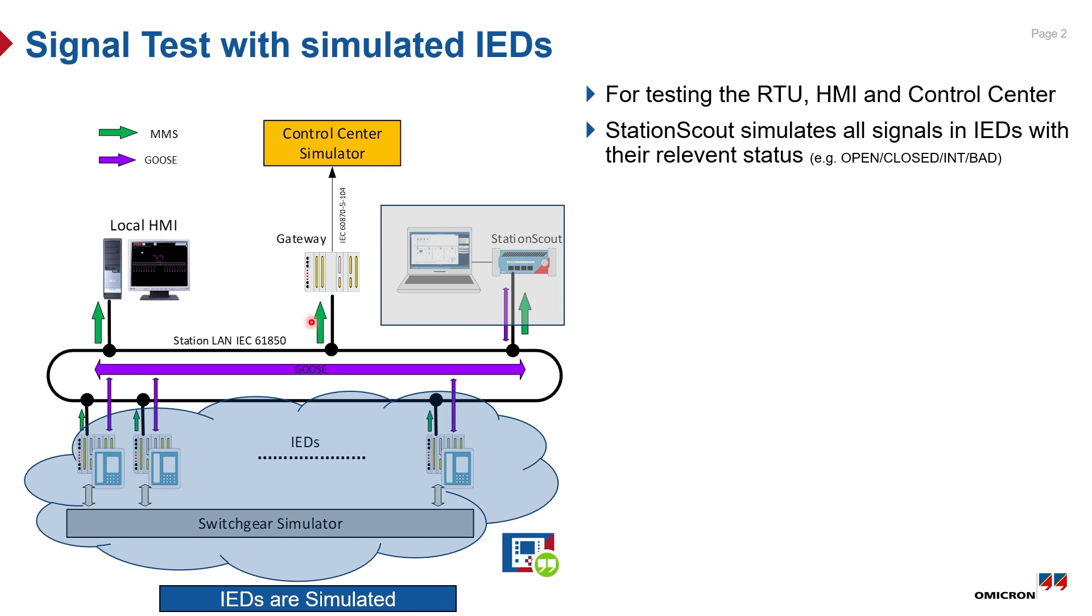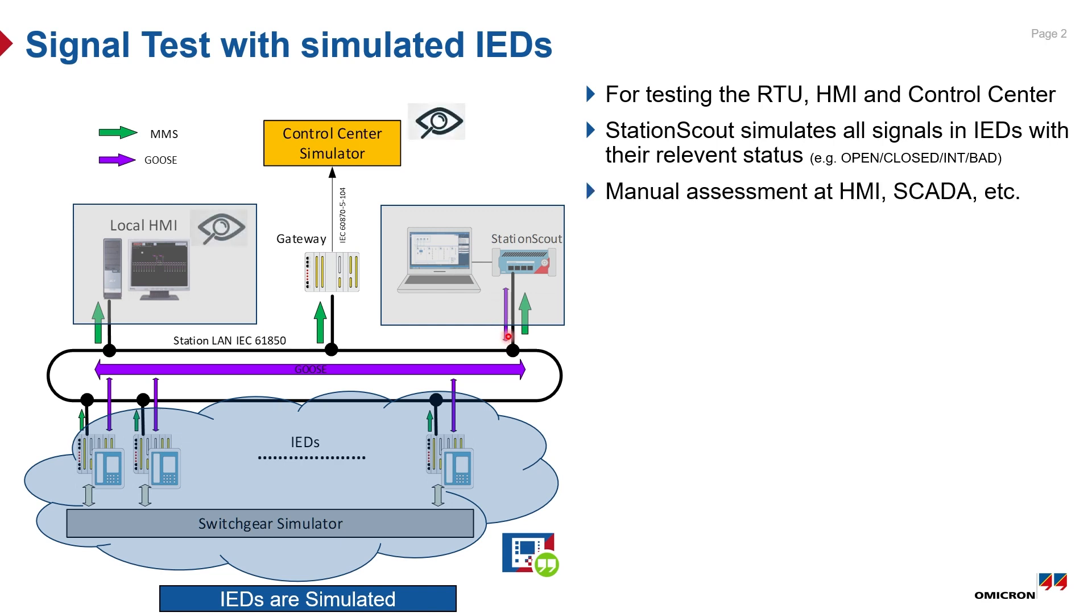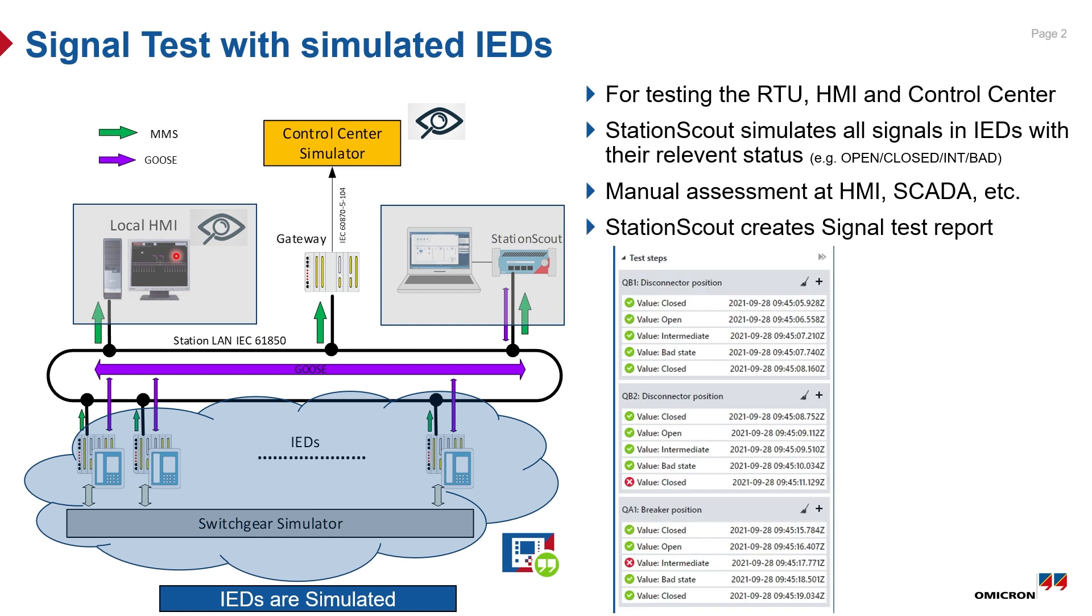Station Scout is simulating all the IEDs in the substation to test if they are sending the correct signals to HMI, and the HMI is using the correct addresses of the signals to process, visualize, and log. The assessment here can be made visually by observing the necessary pages of the HMI. Finally, Station Scout will give a test report for documentation purposes, and you'll be able to save the same test plan for FAT and SAT as well as after firmware updates and during maintenance tests to execute instantaneously.